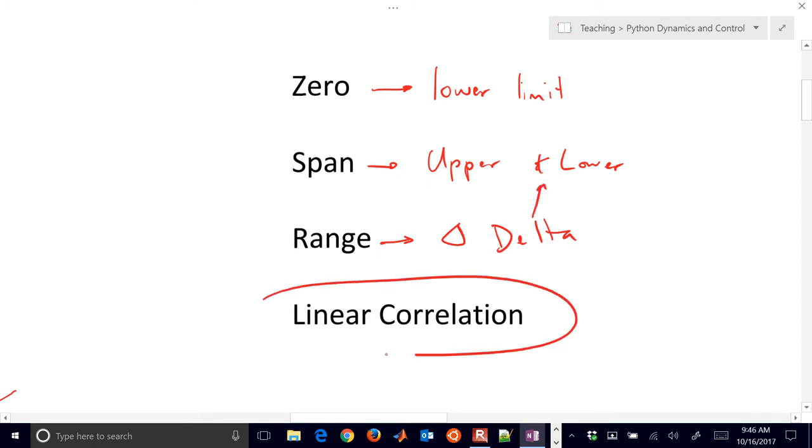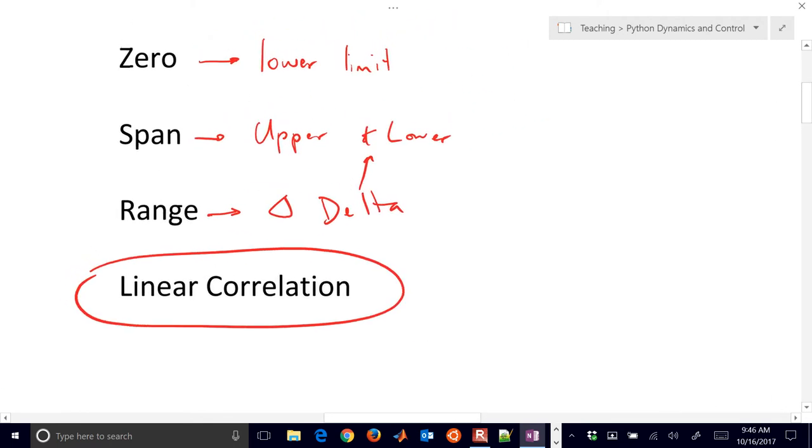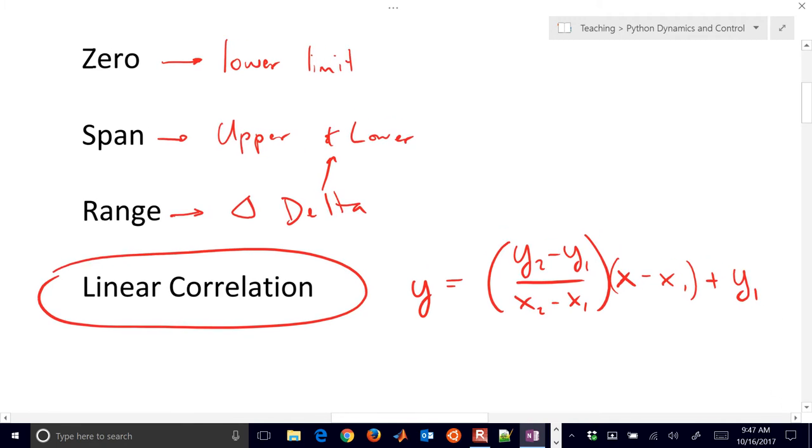And this is the delta or the change between the upper and lower. And then a lot of times we will develop a linear correlation for our sensor as well. So for example, if we want to just do a line, we'll do y2 minus y1, x2 minus x1 times x minus x1 plus y1. And that develops our equation of a line. So that if we have different inputs, we can predict different outputs.